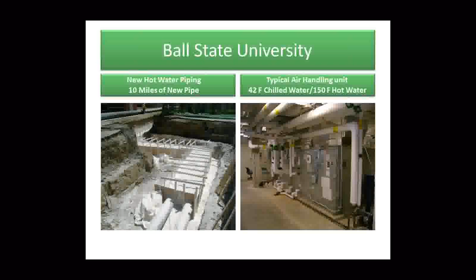A quick diagram of how this was all connected. The old process is a heat exchanger, as you see on the left-hand side in the middle of this diagram. Steam goes in, condensate comes out. We've got a circulating loop of hot water that goes over to the air handling units. All we had to do was reach into the building with our new distribution lines, tap into the return side of that equation. We even keyed off and went to another heat exchanger where we could preheat domestic water, trying to find multiple uses for that thermal energy that we're producing.